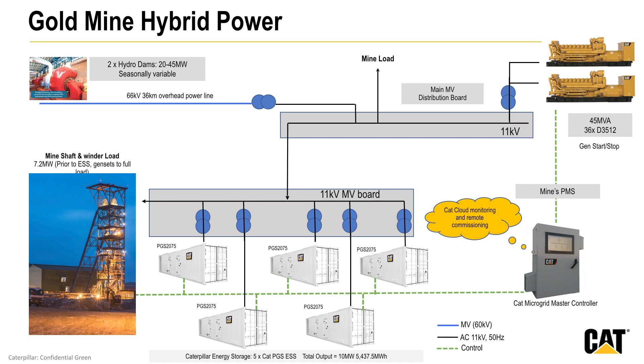The interesting thing about this particular load is when it's bringing the raw materials up, of course, it's consuming a lot of electricity. When it's going back down again, it's actually producing regenerative loads, which are now able to be captured in the battery system and reused. The difficulty prior to the addition of the energy storage system was that the gensets were having to be run with quite a lot of additional spinning reserve or headroom so that this large motor could kick in and out. Adding the battery system has allowed those gensets to be run a lot more efficiently, and the payback period on this particular site was between 2 and 3 years.